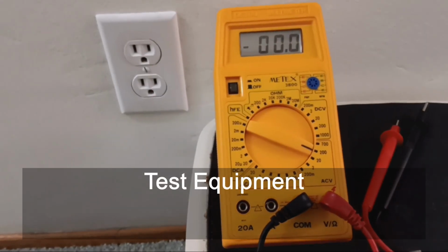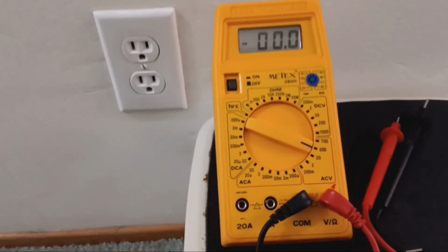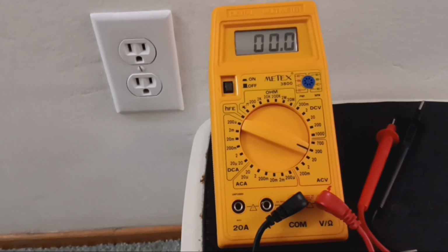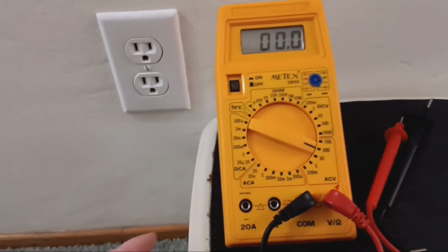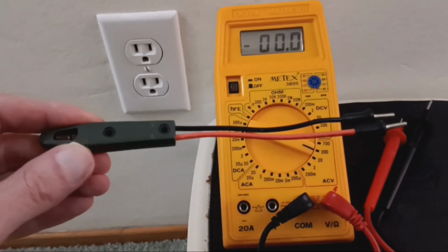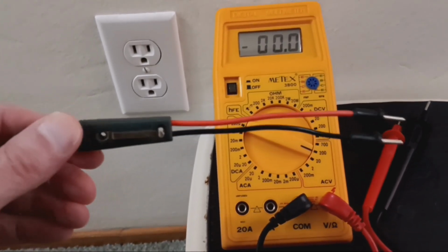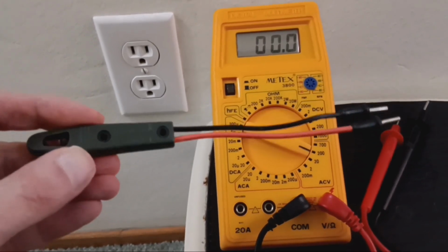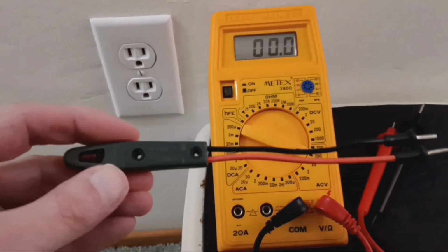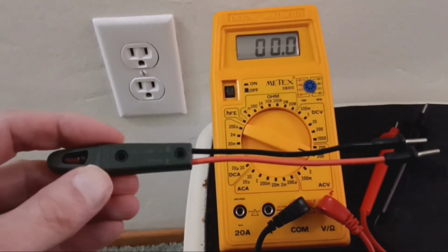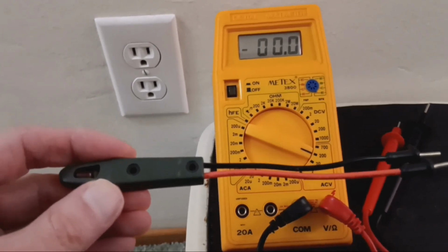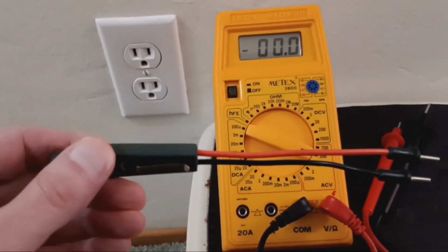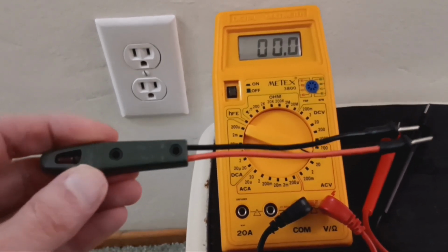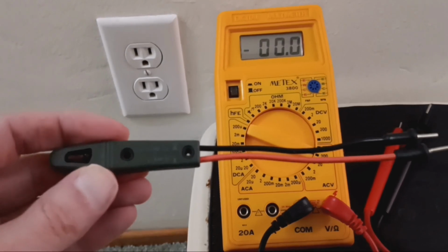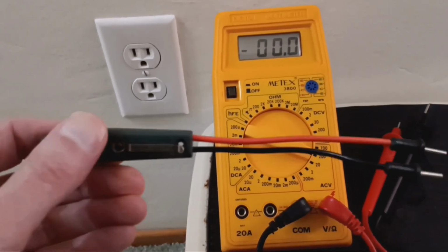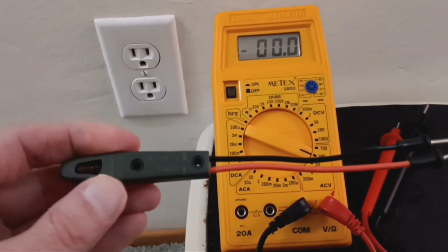I'm only going to show how to test a 120 volt outlet in the United States, and I'm going to show how to test the outlet using both a multimeter and a neon voltage test probe like this. And this is an old neon voltage test probe, so you probably can't get this exact one anymore, but I've seen these on Amazon for around $7. But you can get a multimeter for around $10, so I would get a multimeter instead of one of these, unless you can get one of these for around $1 or less. And don't get the neon voltage test probe confused with a neon voltage test screwdriver, because those work differently.